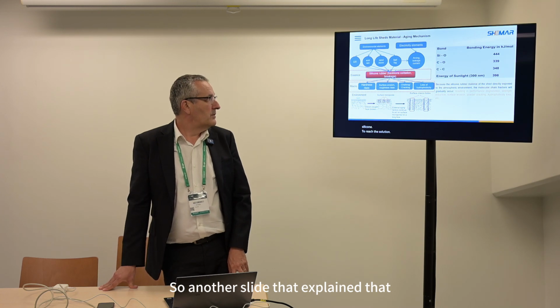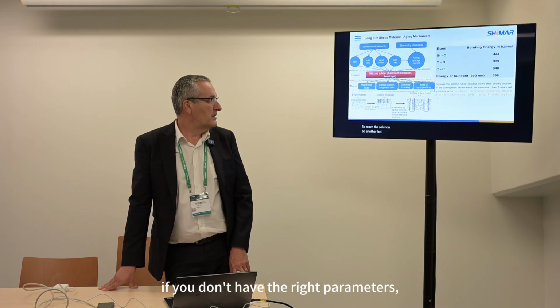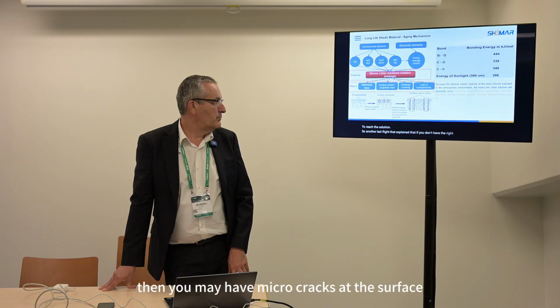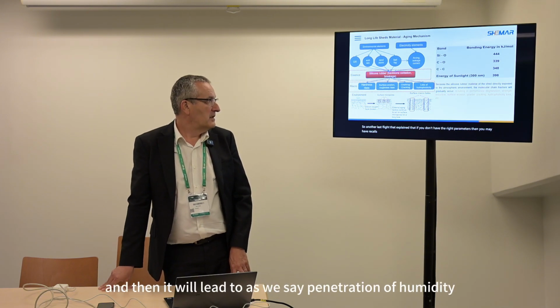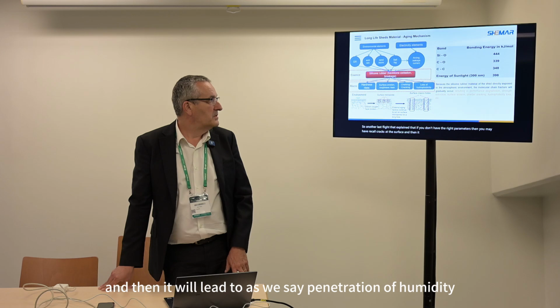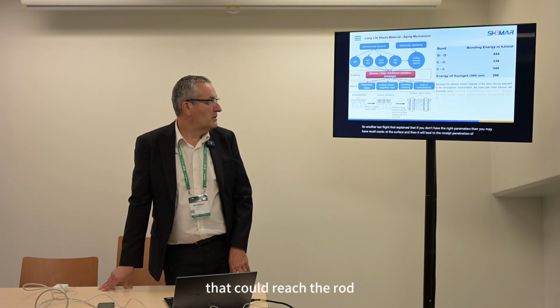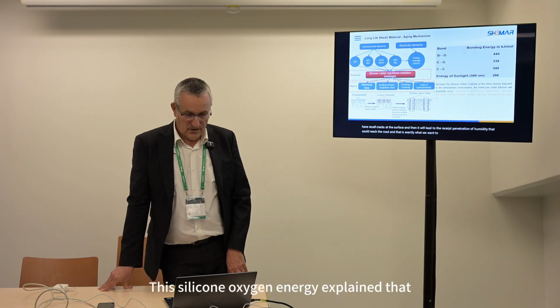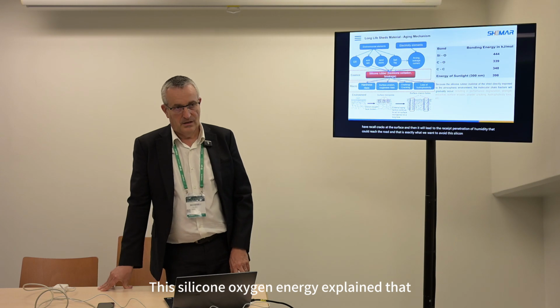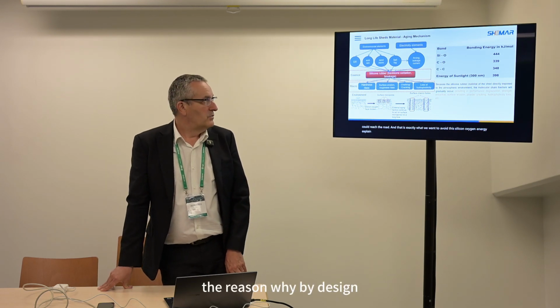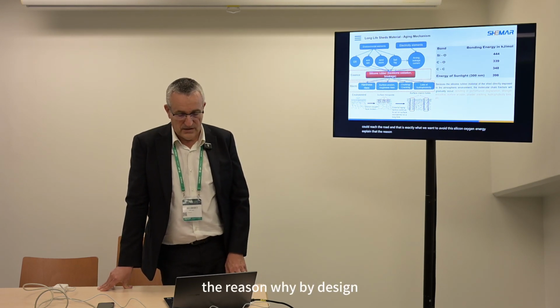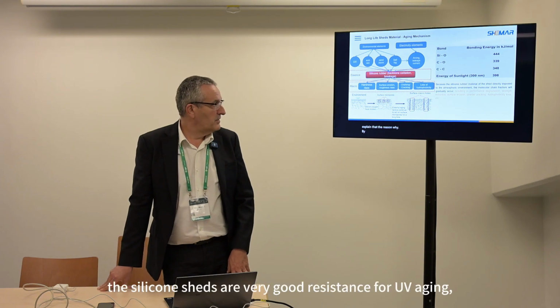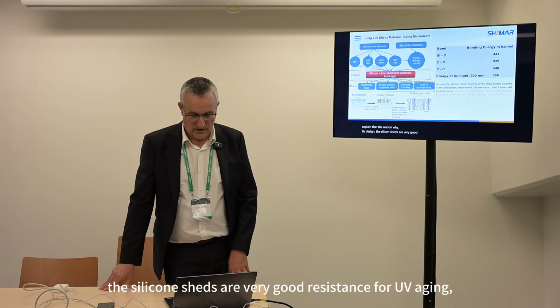Another slide explains that if you don't have the right parameters, then you may have micro cracks at the surface, and this will lead to penetration of humidity that could reach the rod, and that is exactly what we want to avoid. This silicon-oxygen bond energy explains why, by design, the silicone sheds have very good resistance to UV aging.